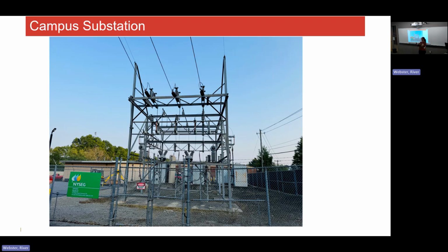You might have 201 and 301. And if there was a problem, and the building's only operating off of 1 feed, in each electric room there's a switch where you turn on, like, okay, I'm operating on 201 and 301's off. So with a lot of campus systems with mechanical, electrical, the redundancy matters, because if you need to do maintenance on one, or if you have a failure on one, you have your backup.